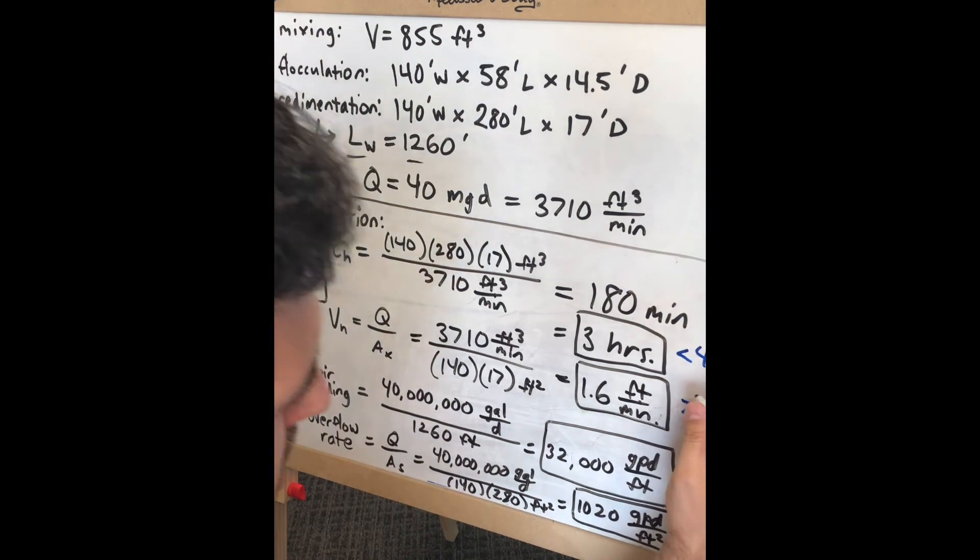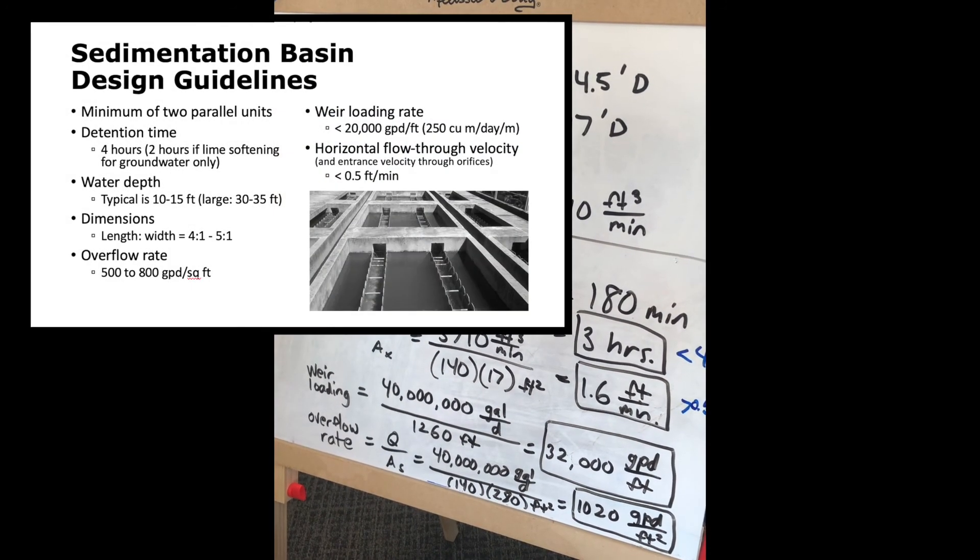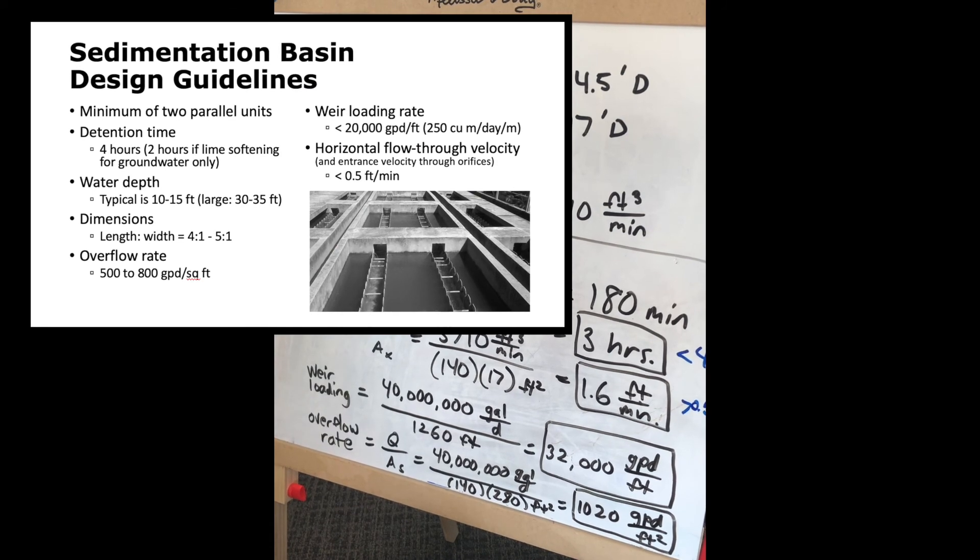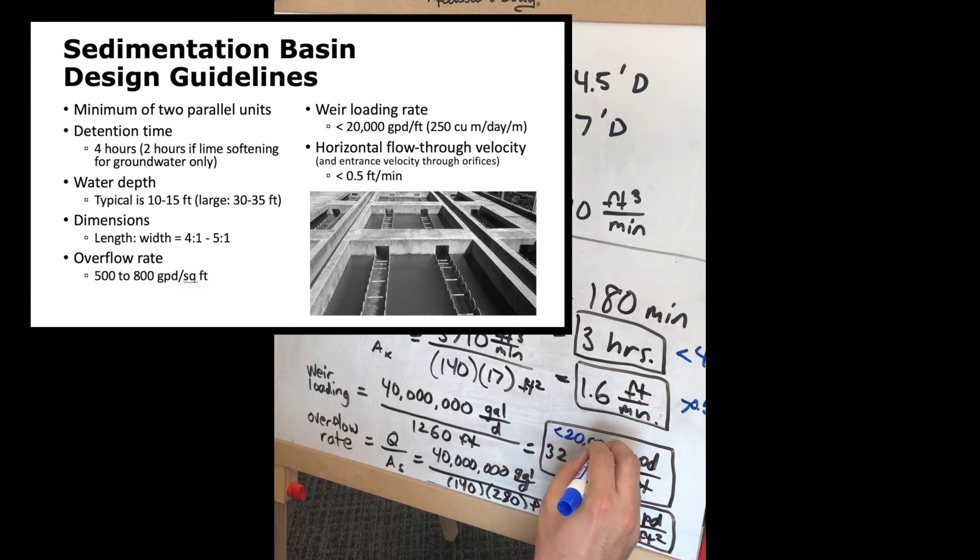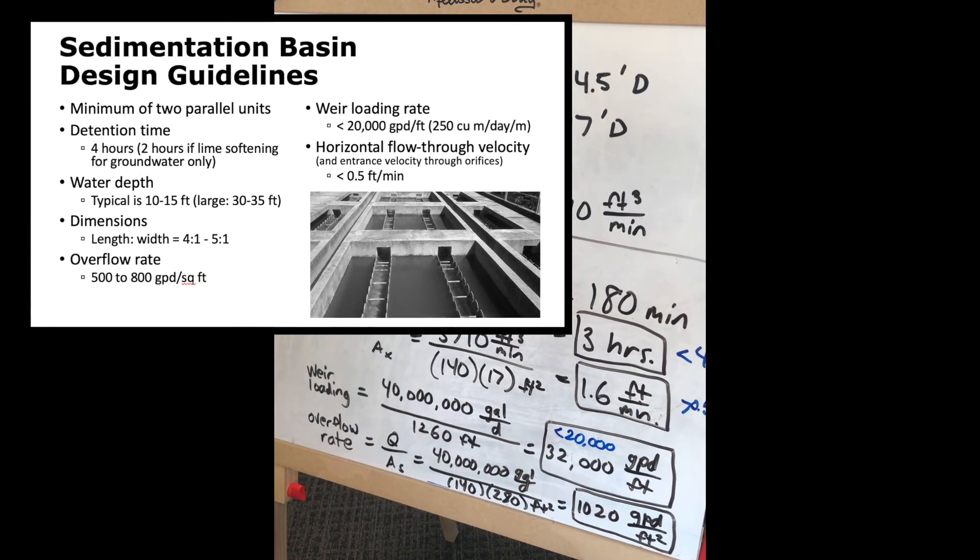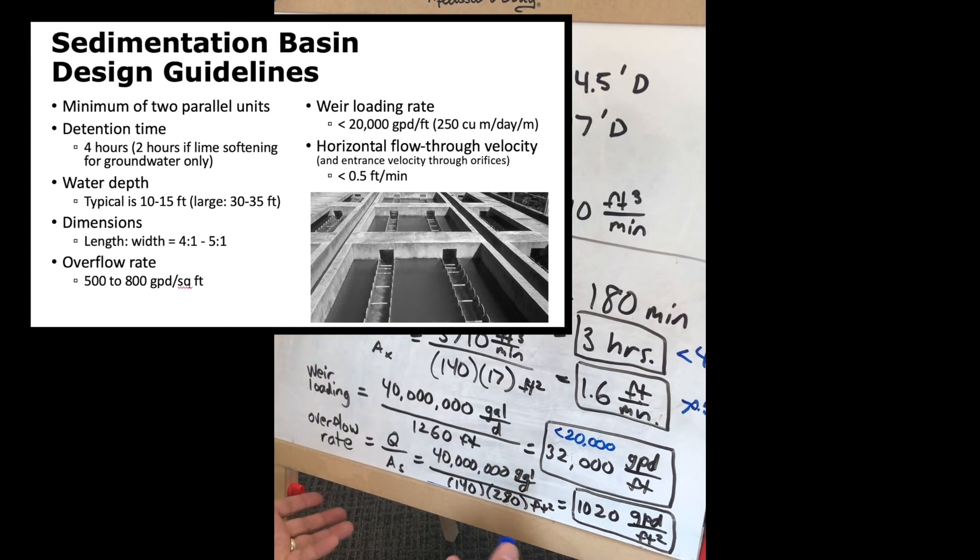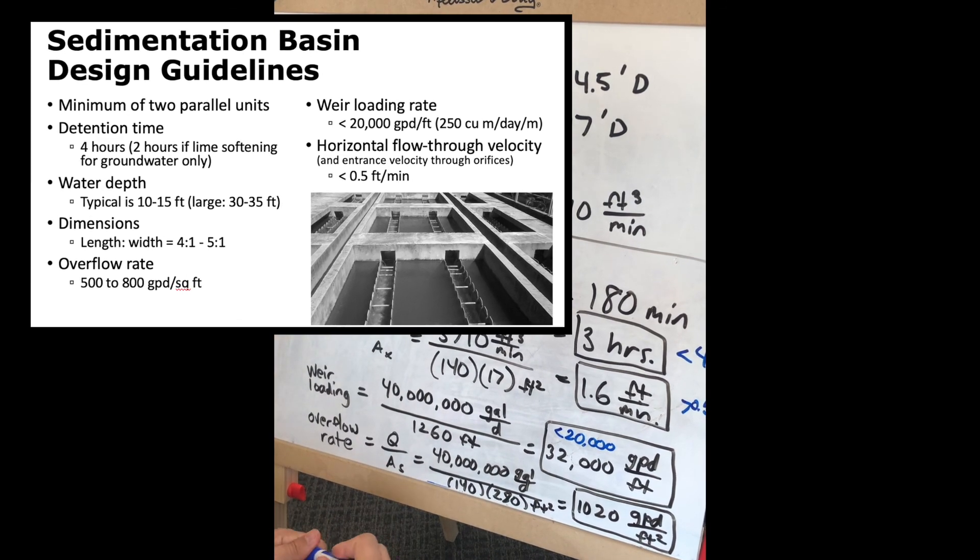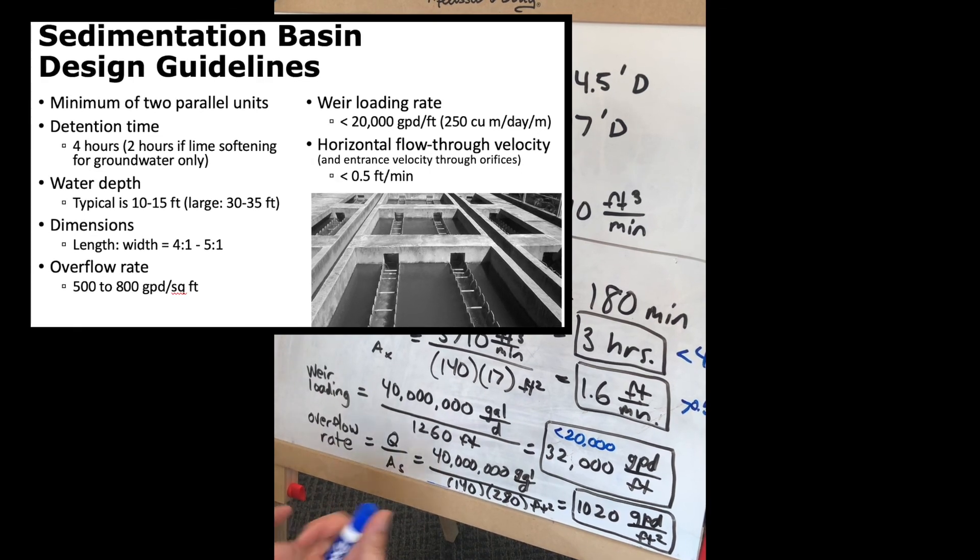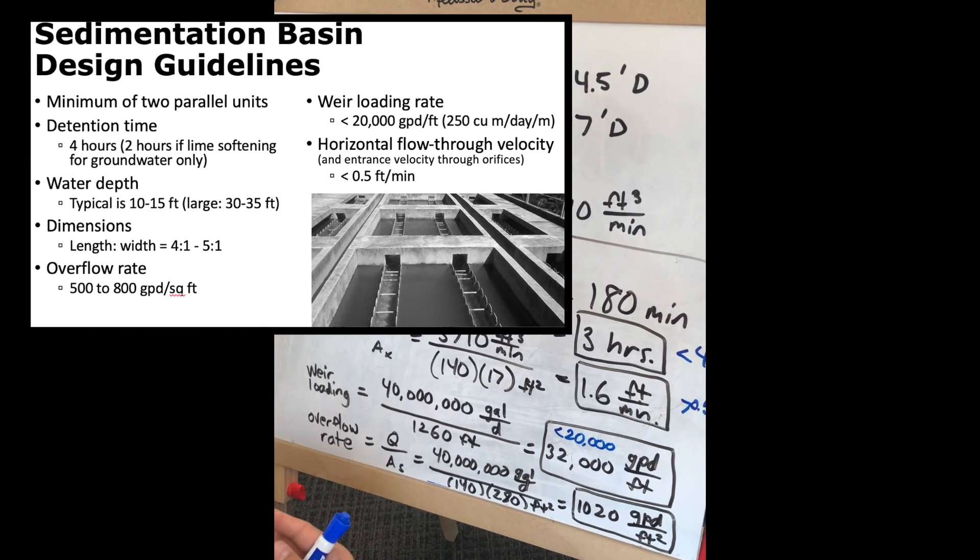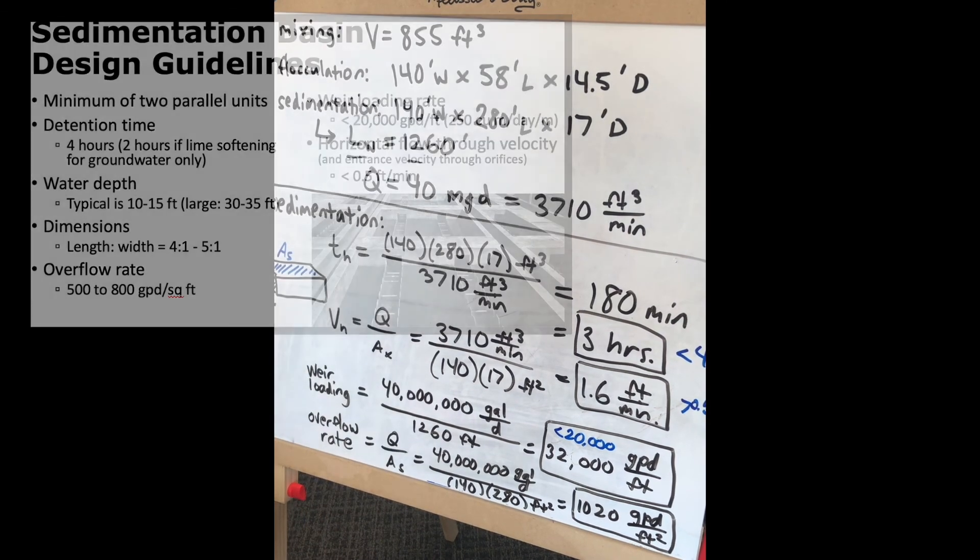We find that three hours is less than the recommended four hours, 1.6 feet per minute is greater than 0.5 feet per minute, 32,000 gallons per day per foot is greater than 20,000 gallons per foot which is the design guideline, and we can do the same with the overflow rate.